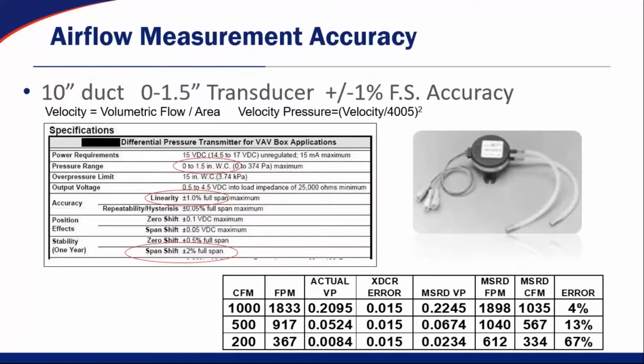Speaking of accuracy, looking at a typical pressure transducer, for this particular example, I'm looking at a 10-inch duct with a 1.5-inch pressure transducer boasting 1% full-scale accuracy. Now, salespeople tell you 1% accuracy is better than Phoenix Control's 5% accuracy, but what they miss is that little FS, or full scale.